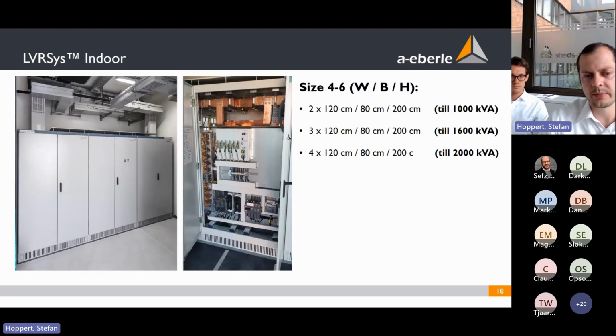And when we go to our biggest cabinets, we use more than just one cabinet. Then we have to put each phase in a different cabinet, and we use 3 cabinets up to 1600 kVA. Our biggest system at the moment that we have built is a 2000 kVA system, and here we have 4 cabinets of 1 meter 20 in width. And of course, with these huge systems, we are not using NH separators, NH switch disconnectors. We are using direct bus bar connection. You can see it in the right picture. It's a really huge bus bar connection.